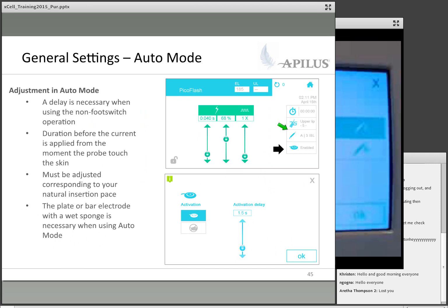Auto mode is working without the foot pedal, and that is the last little box here on our screen. The auto mode means that I can essentially use my probe as a sensor in order for the machine to automatically deliver the pulse without me having to press on the foot pedal. So when I select this enabled button, it takes me to a screen that shows me foot pedal mode or auto mode, working without the foot pedals. You have the circle with the line through it. When I select this auto mode here, this activation delay shows up.